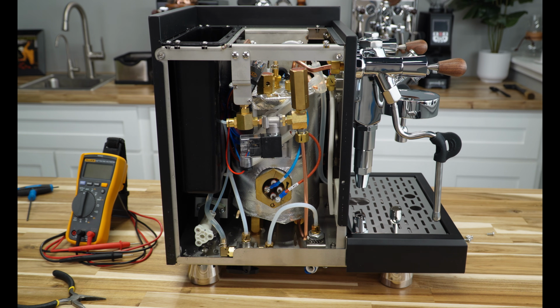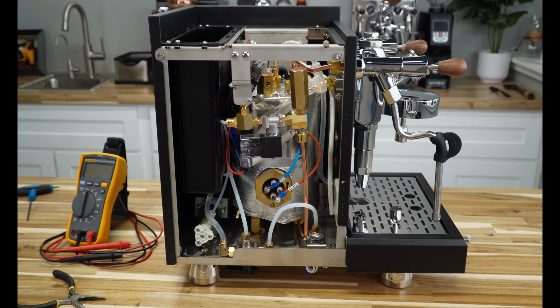We get calls where people say every time they turn it on, it trips their GFCI breaker. There could be many reasons, but 9 times out of 10 it's because the heating element is bad. With really corrosive water, the heating element can get a pinhole in it, and that water essentially trips the GFCI breaker in your house.